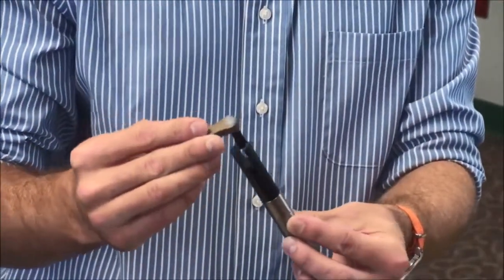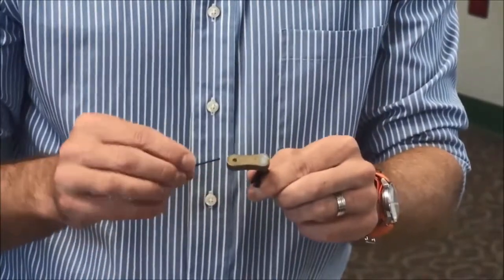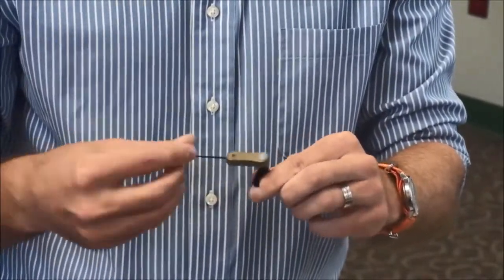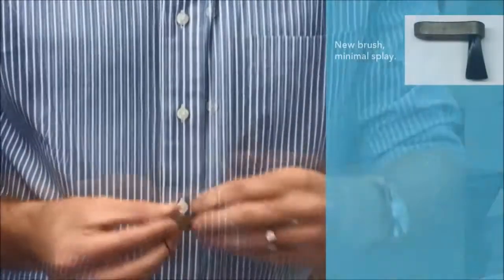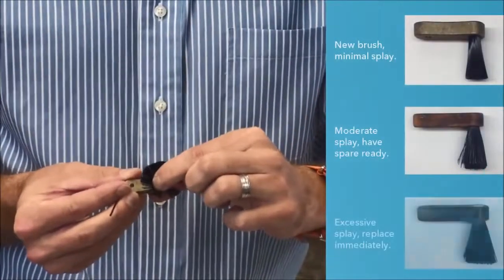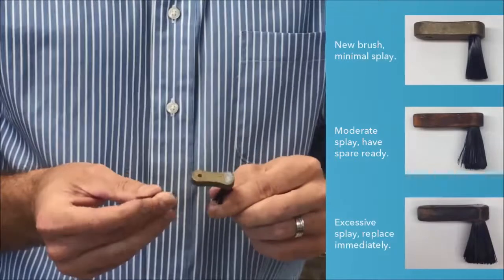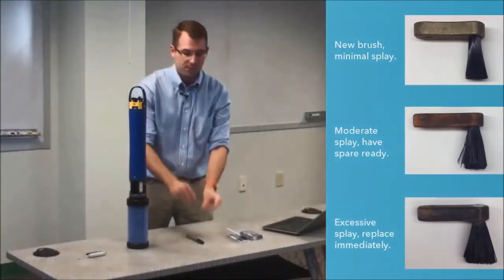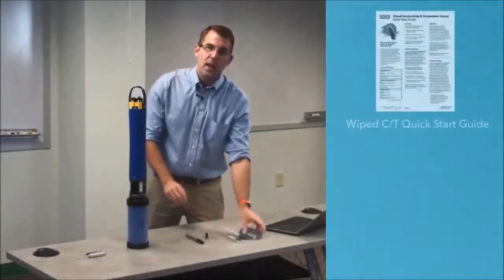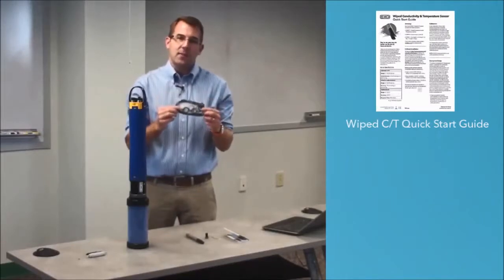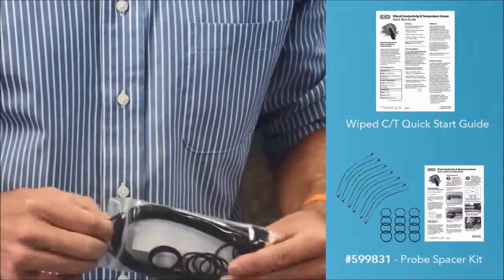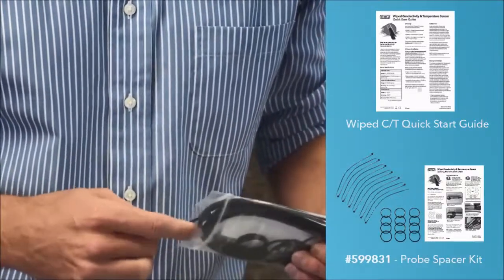We also include a new wiper brush, which we recommend you use new or good condition wiper brushes with your wiped conductivity cell. As this wiper brush splays over time, it adds more resistance and makes it harder for the wiper to properly clean the sensors. We have a quick start guide as well as an alignment kit. This alignment kit is used to optimally space the groove in the conductivity channel with the wiper brush.